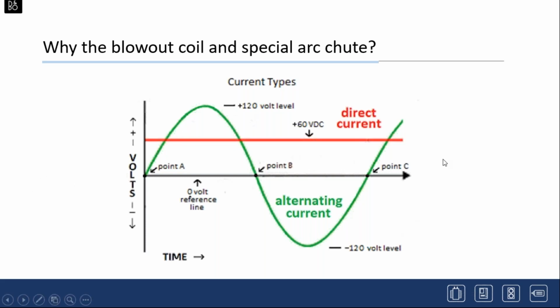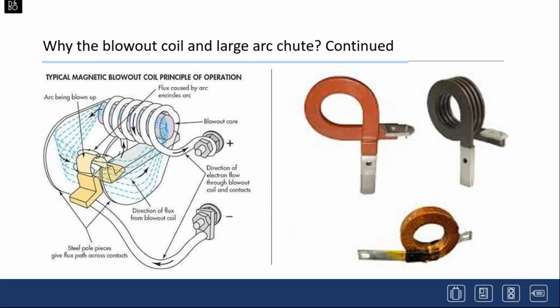With direct current, just as a reference here, if you have 120 volt AC, the direct current is 60 volts DC. Well, if you've got a 480 volt or a 600 volt DC bus, that DC bus is very high and it never goes to 0. So you actually have to, quote, blow the arc out when you're interrupting during normal operation. And to give you a little more detail, we're getting a little more into detail on the DC contactor operation, but I think it's helpful just to understand some of the parts and pieces.